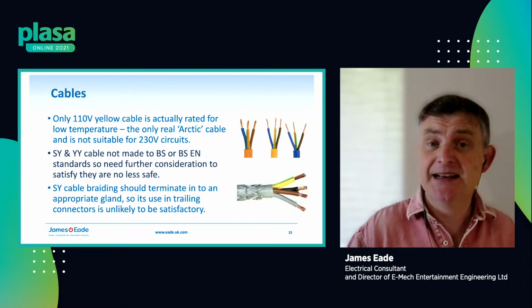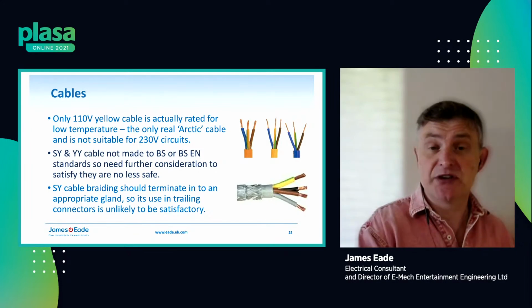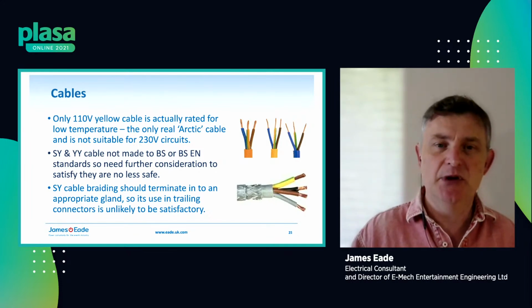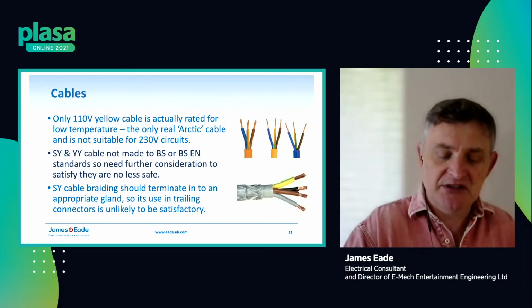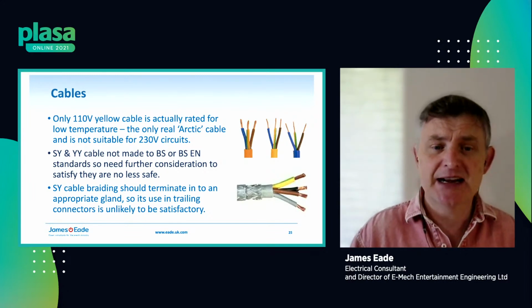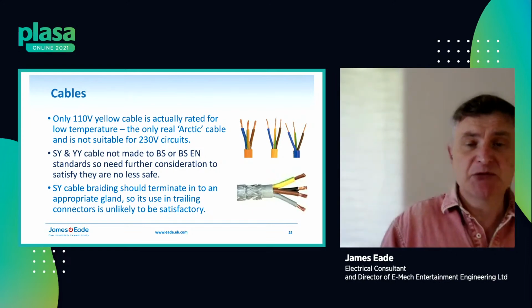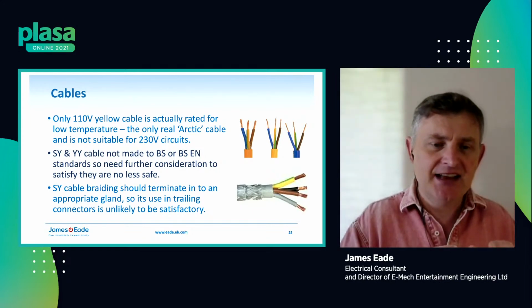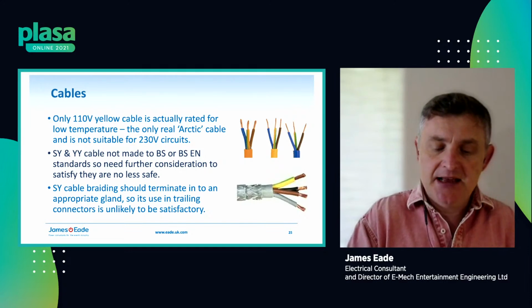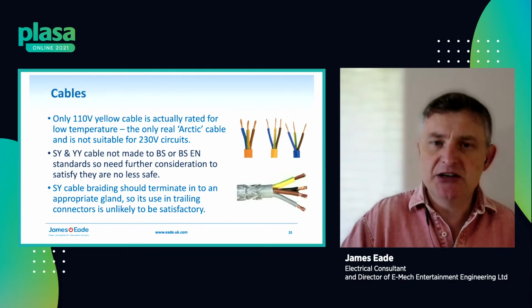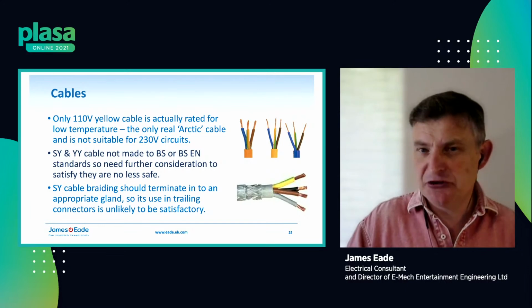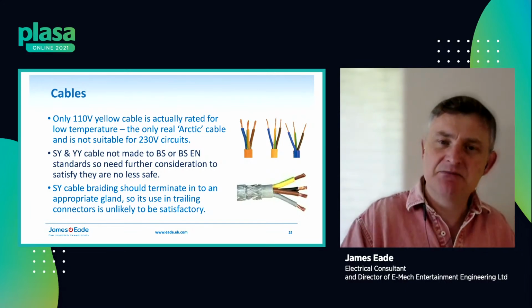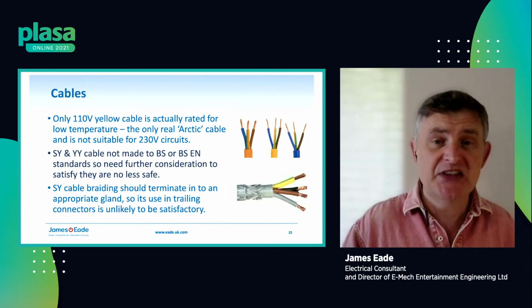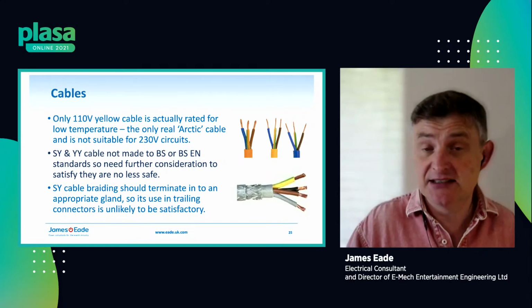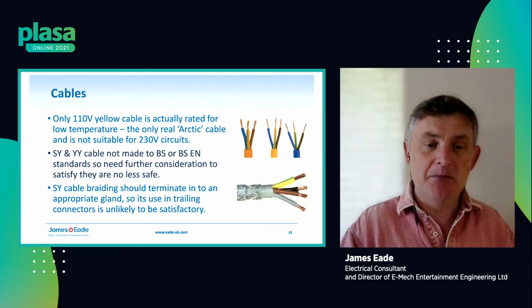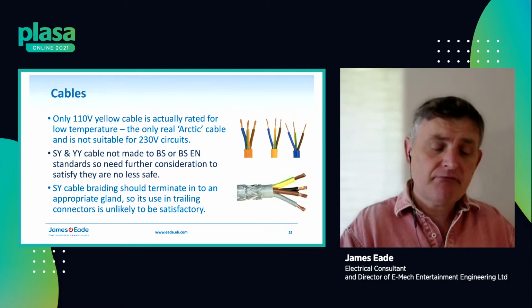Interestingly, if you look at the wiring regs, it says if you're using 230 volts on your building site, use rubber cable to H07RN-F, because the rubber cable has better mechanical protection. On the subject of SY cable, it really is designed to a German standard, not to harmonized European standards. And because it's not constructed to harmonized European standards, for a reason, no doubt, I don't know what it is, obviously it can't comply.